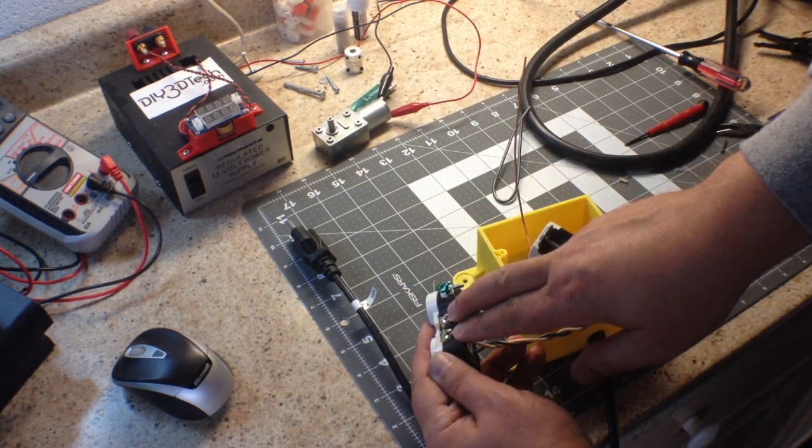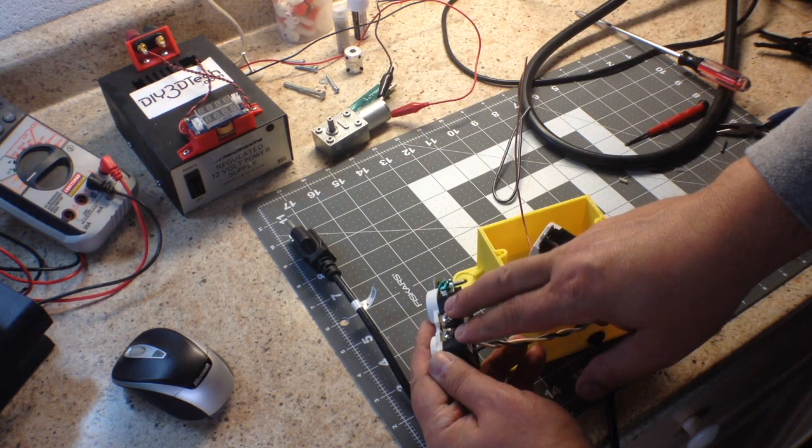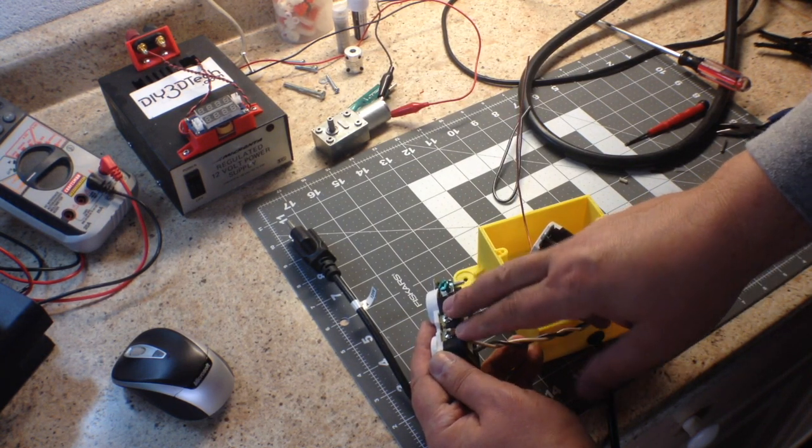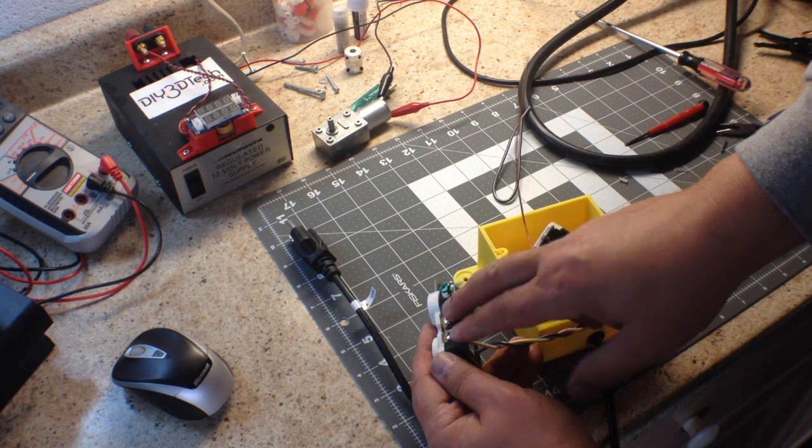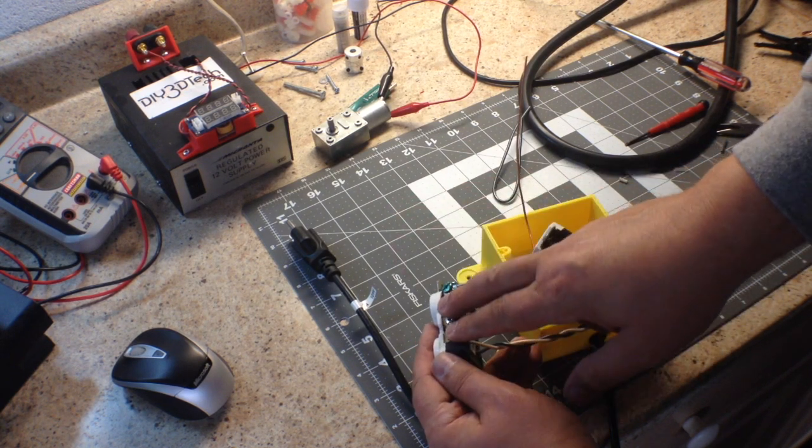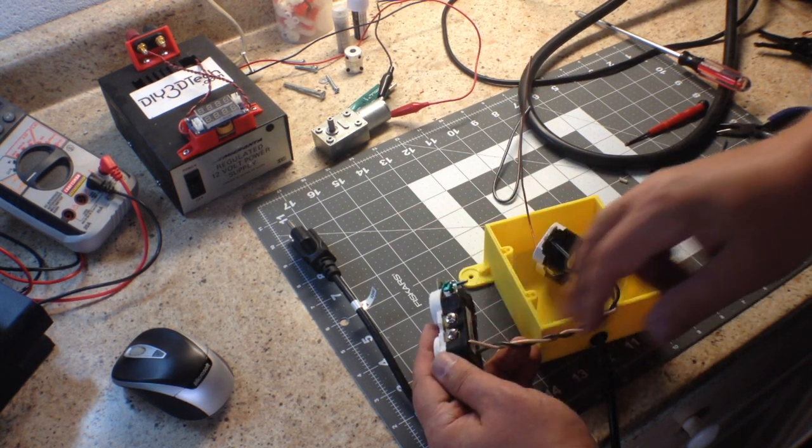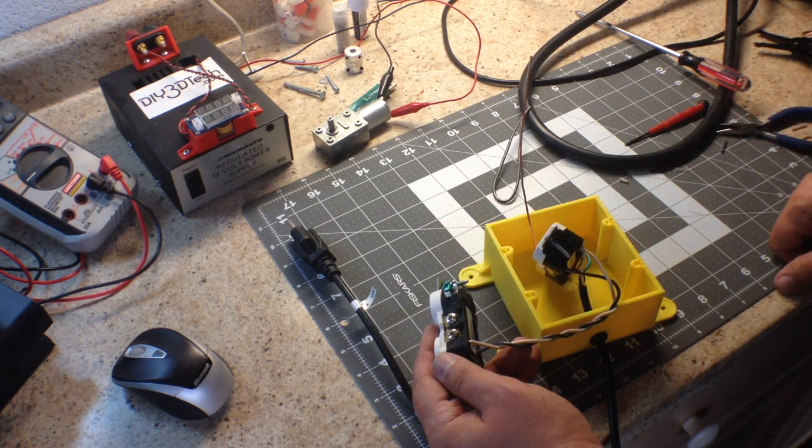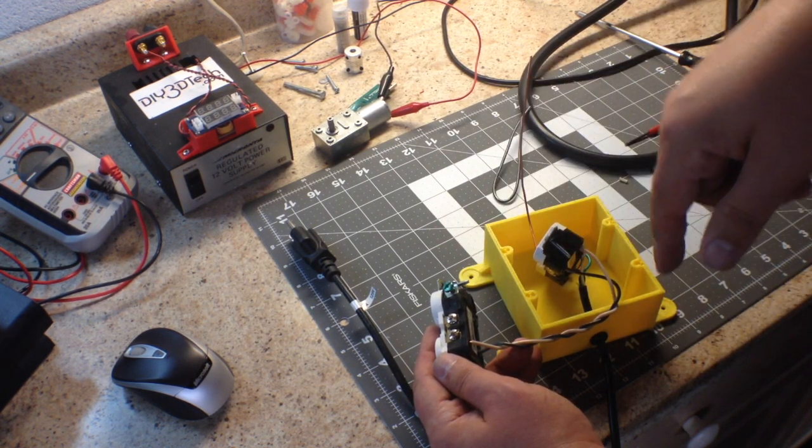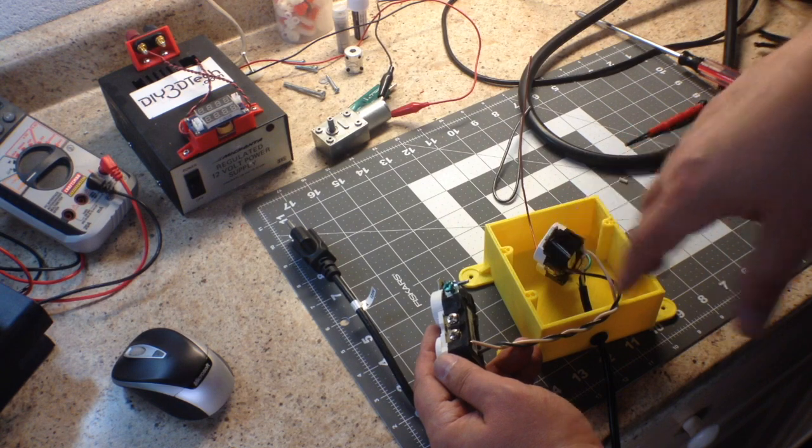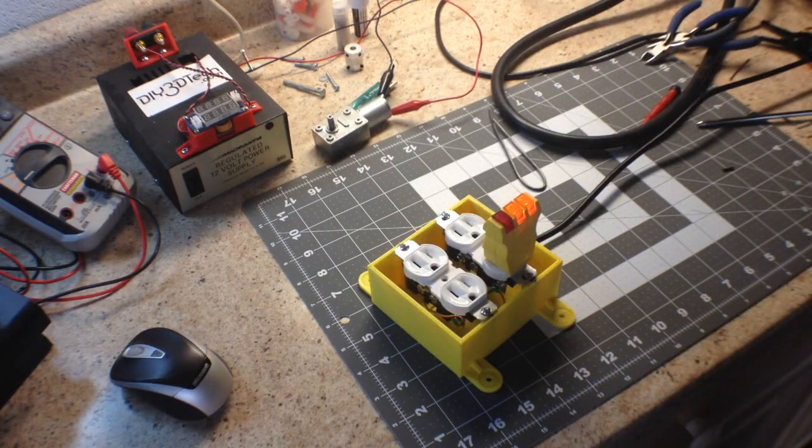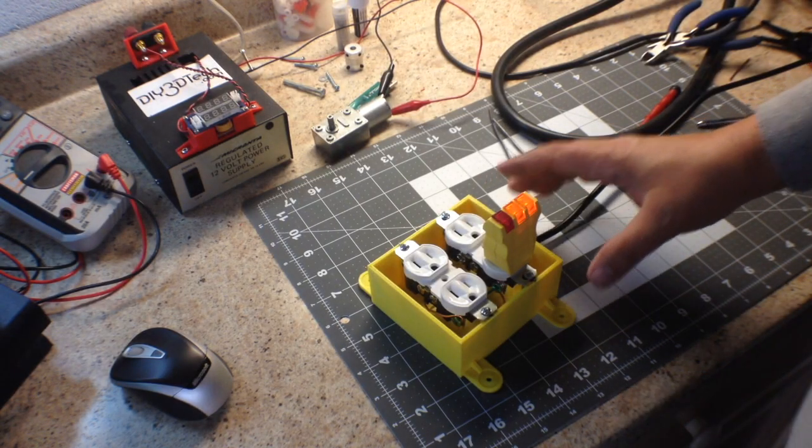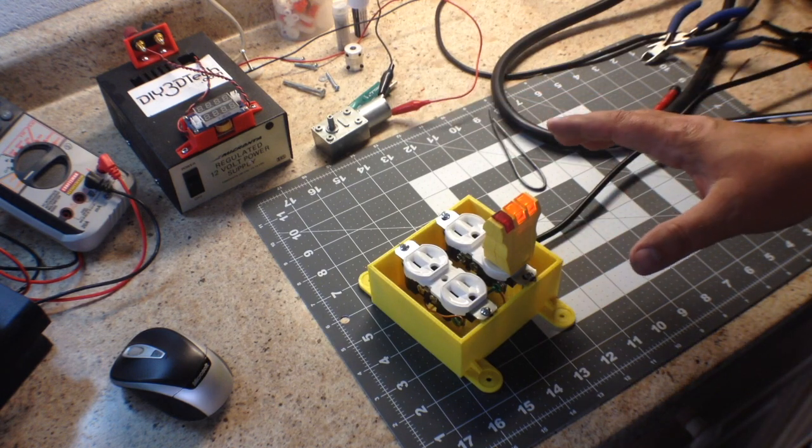Now I would also suggest locking down the lugs here too so they don't short out against something. I've seen a lot of licensed electricians just use the back and then leave these out, and then they bump the box or bump each other. It's just better to do that. I'm going to go back and button this up now and then show you how it all works.